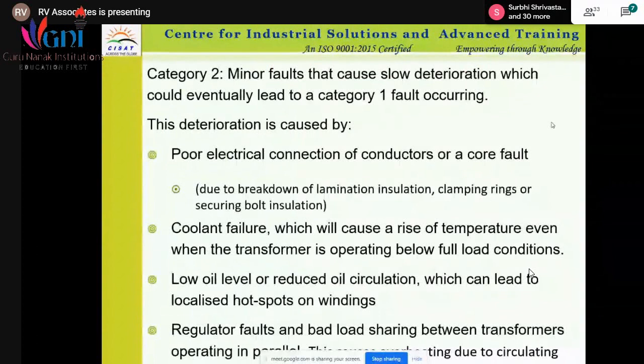Then there may be a failure if transformers are operating in parallel. So bad load sharing is also a possibility that may cause a failure of the transformer, because it's possible that one transformer is carrying more load, and another is carrying comparatively less load. So there will be uneven load sharing, which may lead to a rise in temperature of one of the transformers, and there will be a failure.